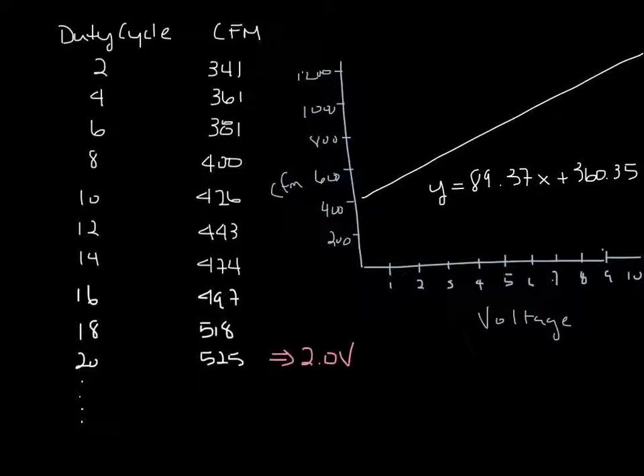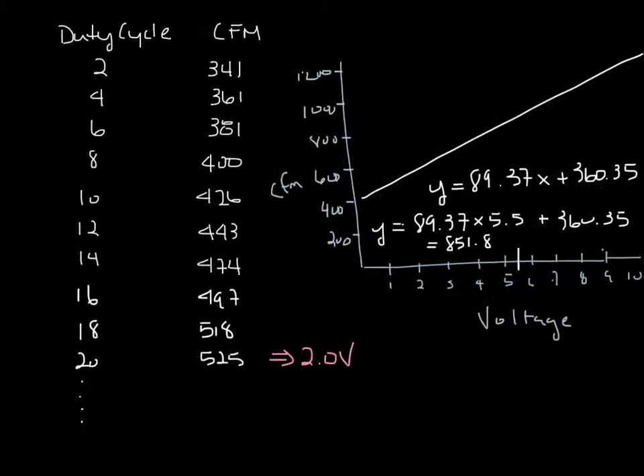Now the controls contractor can put this equation in his DDC controls, and using this equation plus what we call a remote PWM, he can send a voltage signal to the PWM to get the CFM output they want from the fan box. So say a 5.5 volt signal to the PWM would correspond to the duty cycle of 55%, and it would give, if you plug it into the equation up here, 851.8, or let's call it 852 CFM from the box.